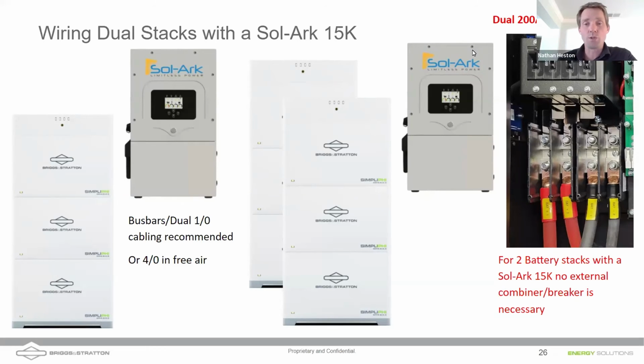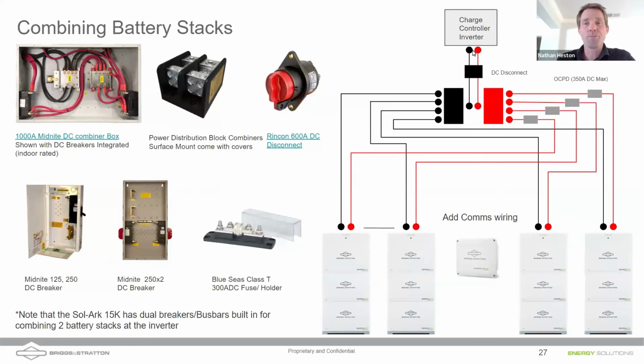where if you're using 2 sets of batteries, you're going to have an external combiner. If you're doing large systems, you might need a combiner. I'm showing the 1000 amp Midnite combiner in the top left. And on the right side of the screen, if you're going to do multiple inverters and multiple batteries, you are going to have a combiner if you're going for more than 2 stacks. Additionally, you will need to have a single gateway for those stacks, and you'll want to have overcurrent protection on that cabling.